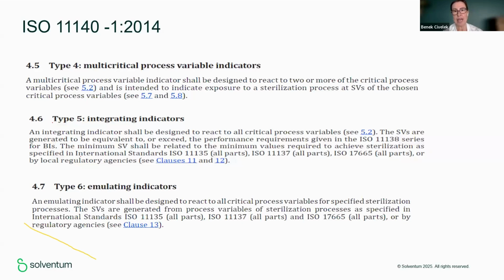For steam, we have three variables: time, temperature, and saturated steam. For hydrogen peroxide, again, we have three: time, temperature, and this time hydrogen peroxide concentration. So if we are talking about three variables and if we want them to be achieved inside each pack, it will be the right decision, in fact, to choose an indicator which will react to all critical variables. For that reason, type 4 will be providing us limited information.